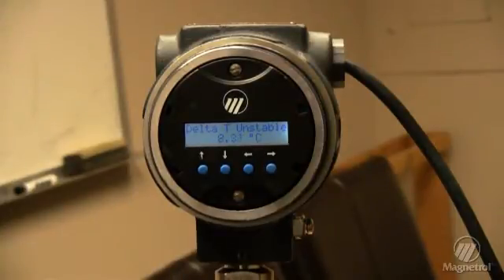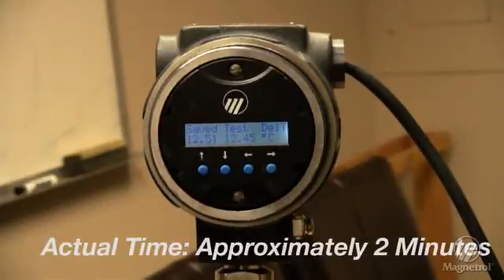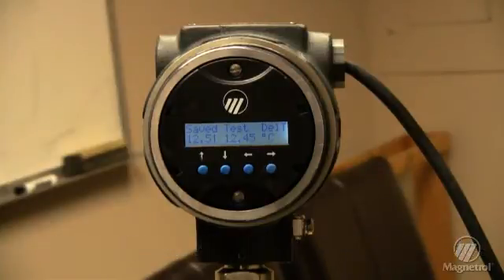In a short time, the temperature difference will stabilize and the two temperatures will show on the display. One is the original temperature difference between the sensors as it left the factory, and the other is the new temperature difference measured. If the values are within 1.5 degrees, the unit is still within calibration.